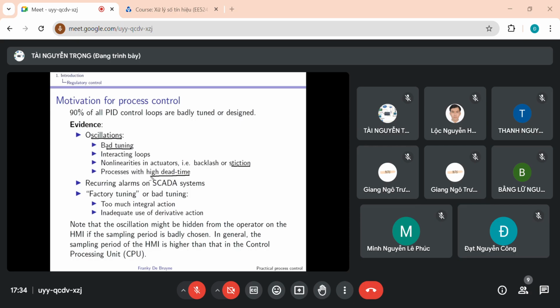Processes with a high dead time, and also non-linearities. It could be that around one working point everything is working properly, and then you change working point and suddenly you see oscillations. This is because the process has changed, and what you can do then is use scheduling, as we will see later on in the course. Another sign is alarms that are coming back on the SCADA system, and factory tuning.